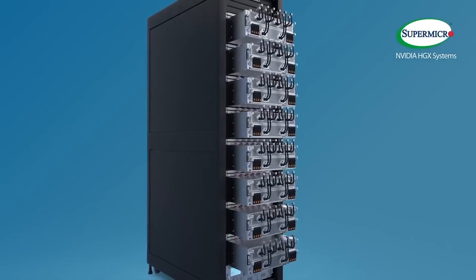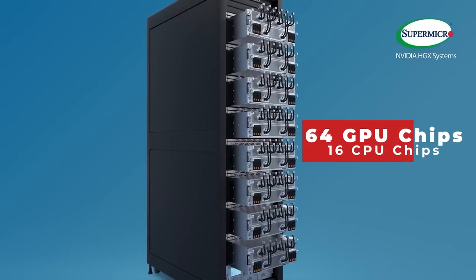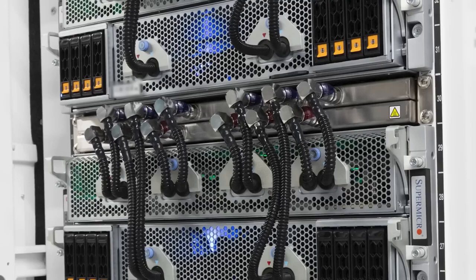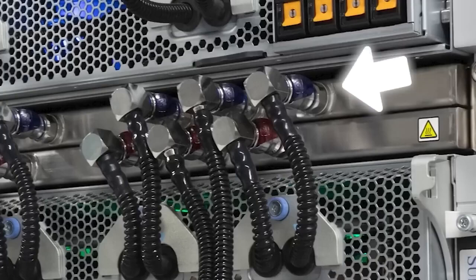There are 8 of these racks built into one cabinet, with a total of 64 GPU chips and 16 CPU chips in every vertical stack. Each of the racks has its own independent water cooling system with small tubes that lead directly into the GPU housing: blue tubes for cold water delivery, and red tubes for hot water extraction.